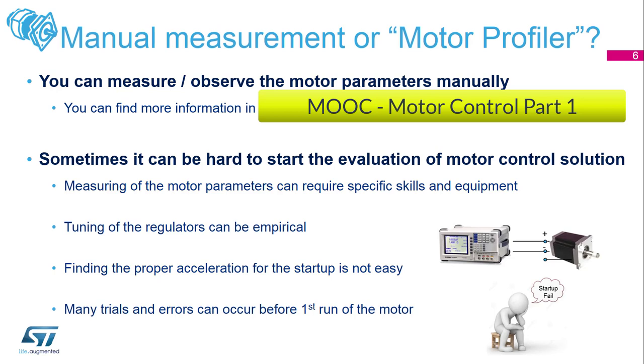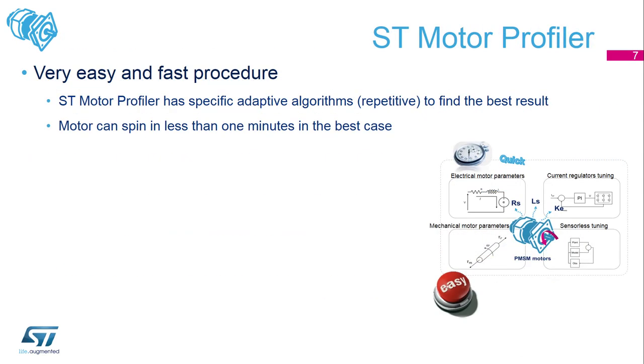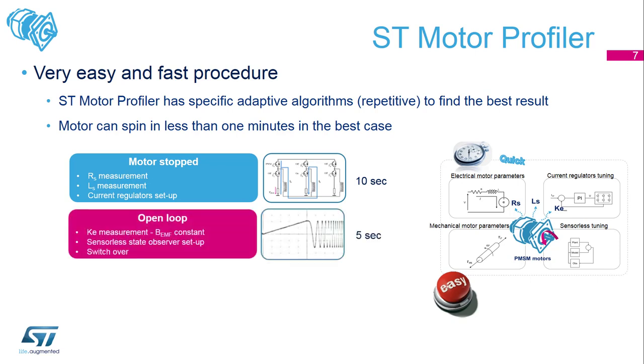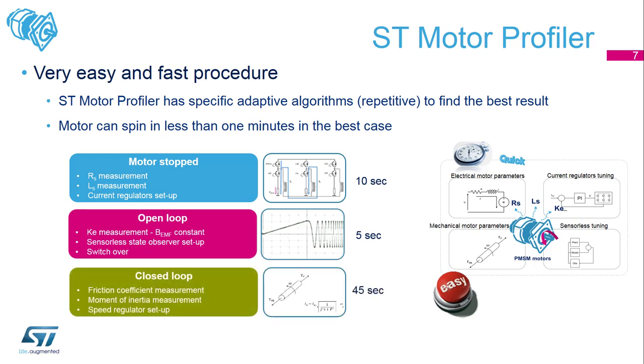With the motor profiler it's a nice easy task — you'll see it for yourself in a few minutes. It takes less than one minute, whereas doing it manually can take a few hours. It will do tests while the motor is stopped, measuring resistance and inductance of each coil and winding, then an open loop test to work out the back EMF for the sensorless setup, and finally a closed loop test.